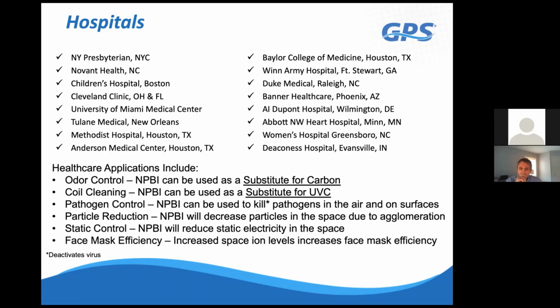If you don't do that, you could have a huge mass of carbon in your air handler and it does not control the fumes effectively. So with carbon, number one, you have to tune it. And also it likes to absorb water vapor before any other contaminant. So a lot of times in hot, humid environments, it's used the majority of its capacity on the water vapor versus the contaminants you're really trying to pull out of the air.